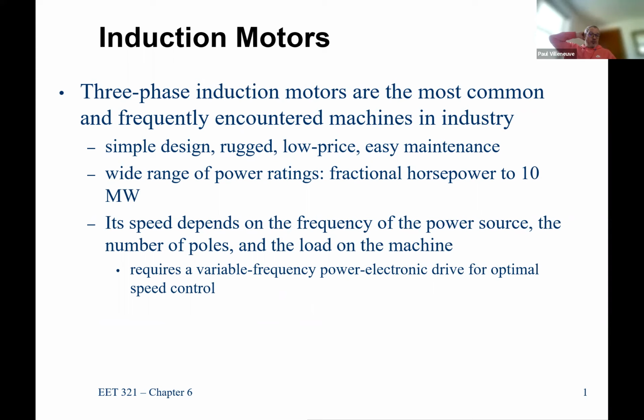So Tesla vehicles used to use Tesla motors or induction machines to do that. They've changed to synchronous machines because of some efficiency, but the concept is the same. When you push your accelerator down or up to get speed, you're just monkeying with this frequency. That's all you're doing. So the same thing applies for induction motors.